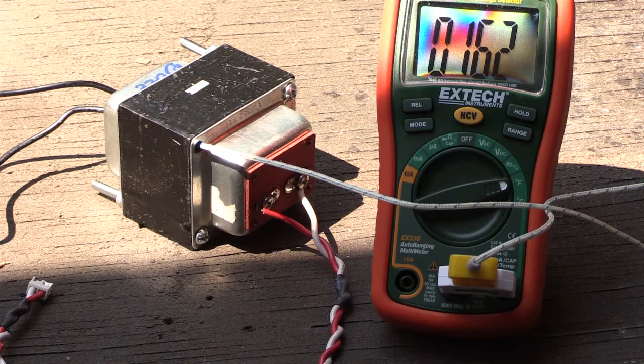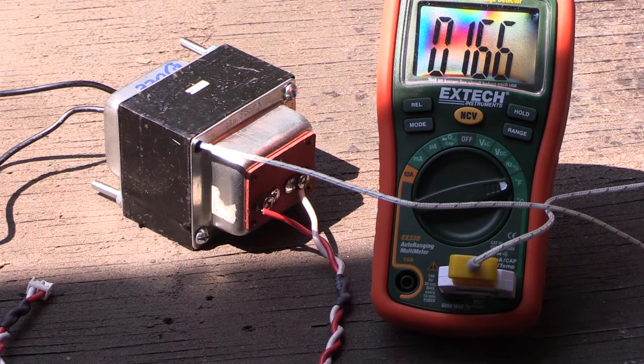The fuse is a safety device, and the transformer is UL rated for the fuse inside the unit. The point of this part of the video is don't modify the transformer. Don't take the fuse out. It's a safety device. What you have to think about is that while we didn't get flames and sparks and smoke and running and screaming because the transformer blew up dramatically, what we have here is a transformer that's on full overload. It has 0 volts output because it's putting out to a dead short.